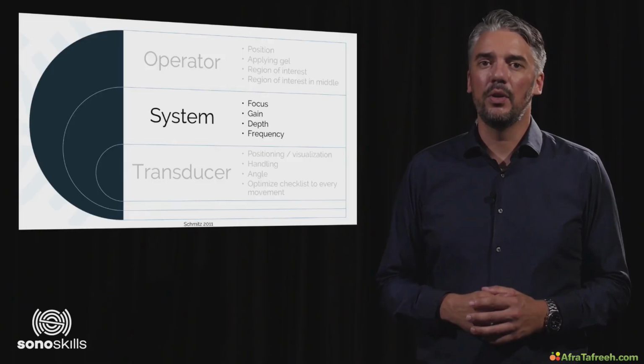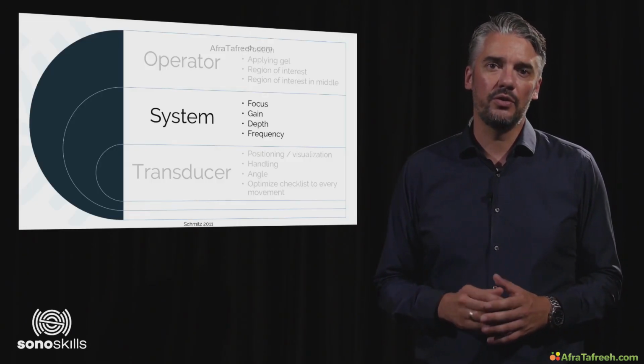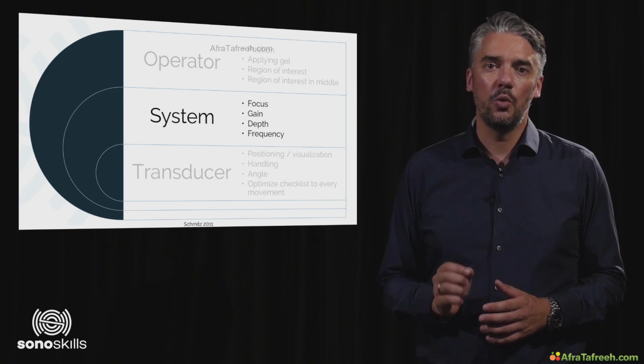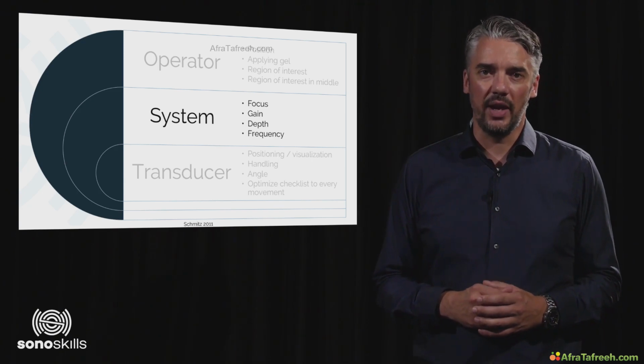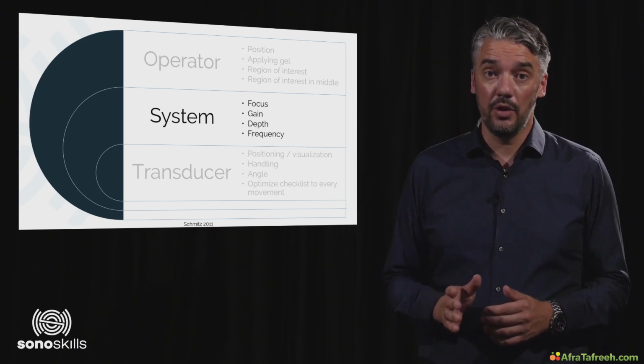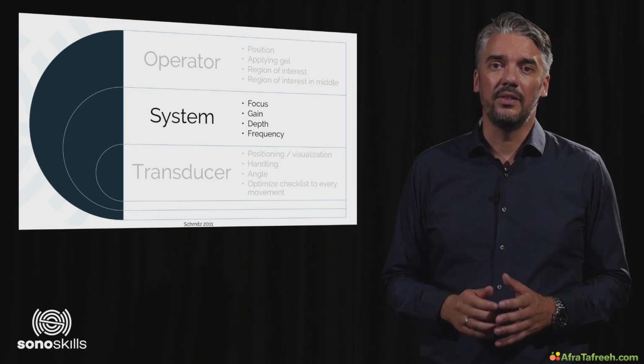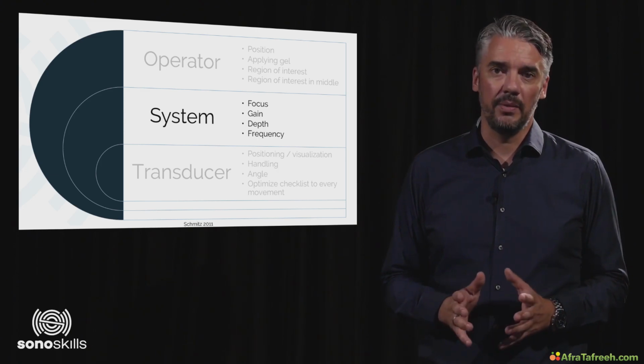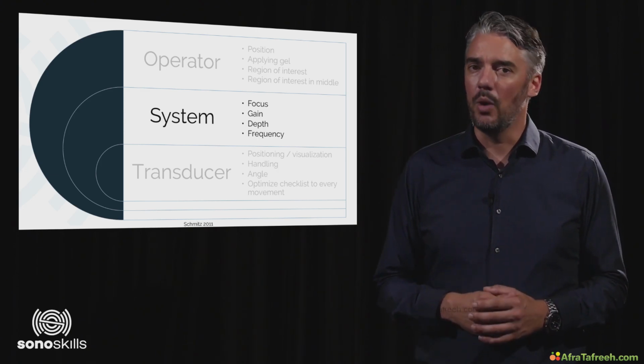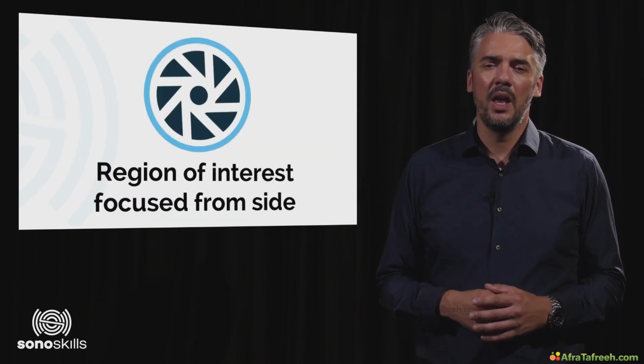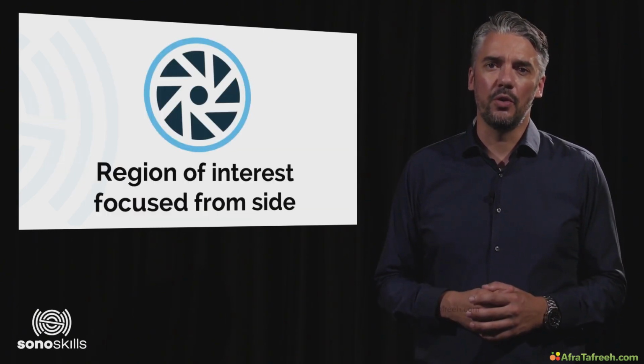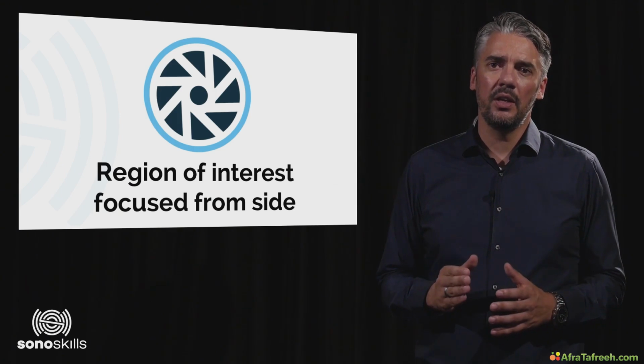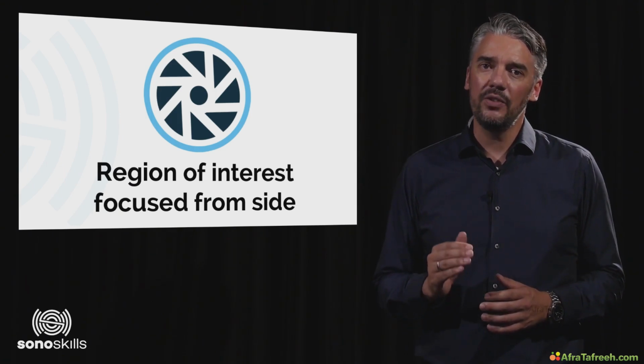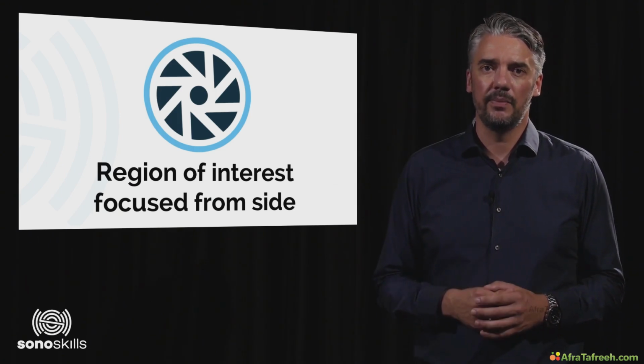The system variables are the second point on our 3x4 scanning quality checklist. The 4 system variables to constantly check and adapt are the focus, the gain, the depth, and the frequency. Let's go over them one by one. The region of interest should be focused. By focusing the region of interest, the greatest degree of clarity is obtained.